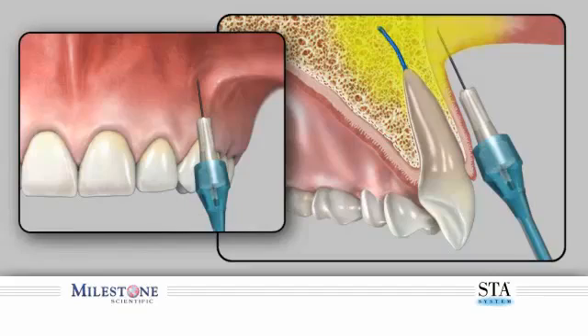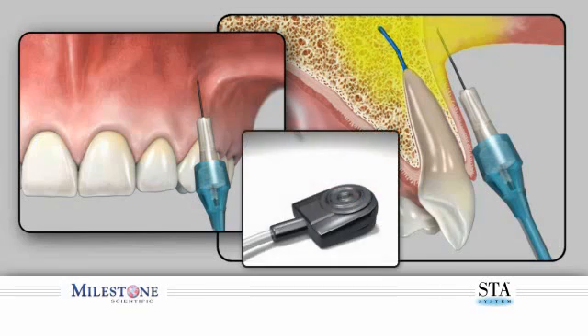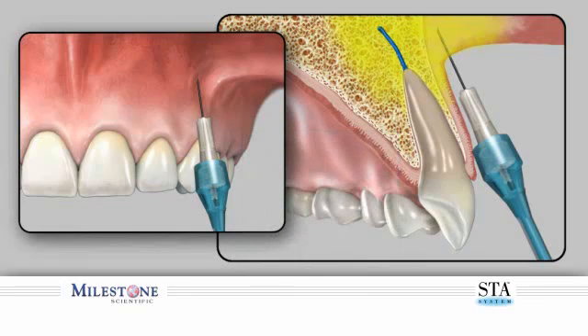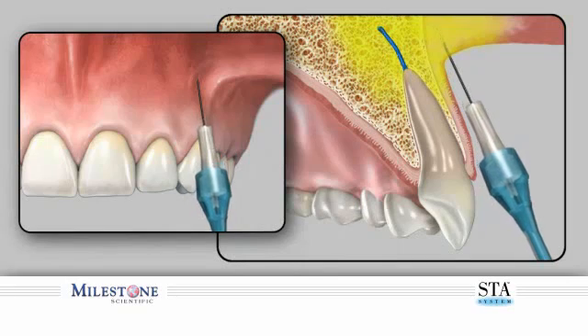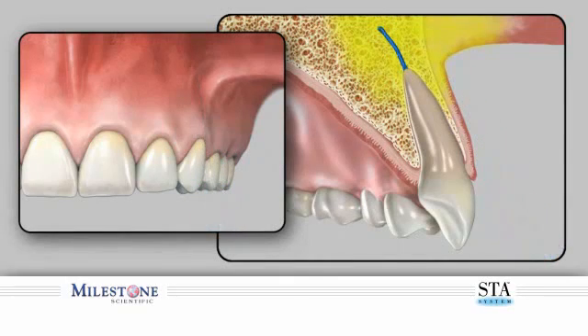When you have delivered the required dosage, you can remove the needle. To avoid anesthetic solution spray back into the patient's mouth, perform the following: while the needle is still embedded in patient tissues, depress and release the foot control pedal. Count three beeps after releasing the foot control, and then remove the needle from within the patient's mouth. Direct the needle away from the patient, as a small amount of anesthetic solution may still be present.